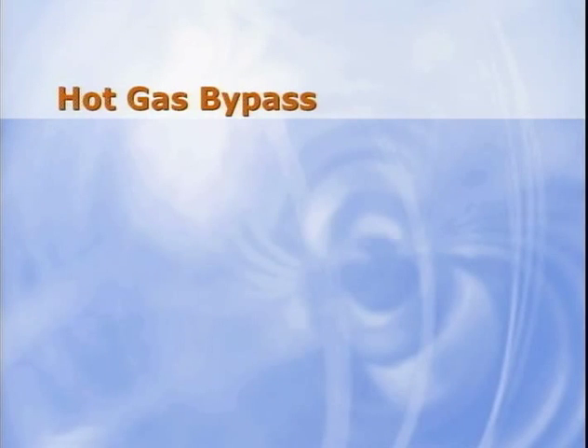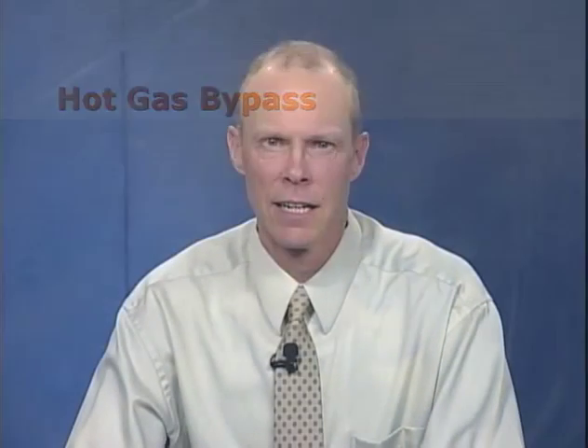Next topic, hot gas bypass. As Justin alluded to earlier, hot gas bypass is probably the device whose indiscriminate use results in more wasted energy than any other single refrigeration design issue I can think of. That isn't to say hot gas bypass should never be used, but for proper reasons, it should either be designed into a system or designed out of the system.